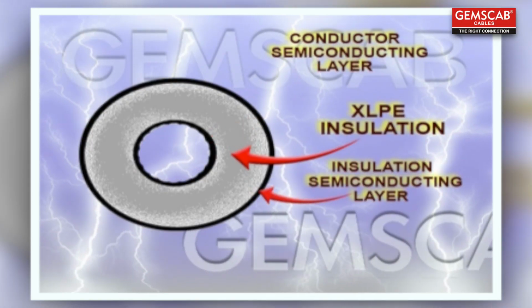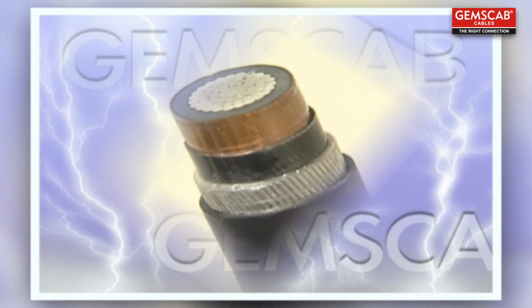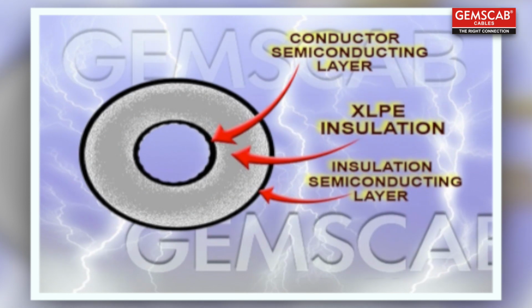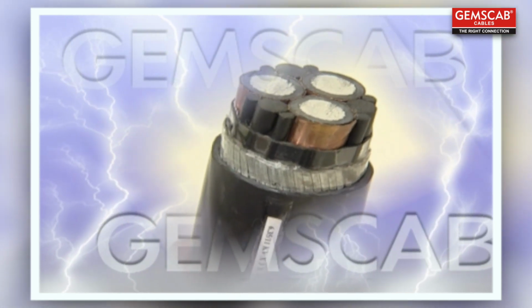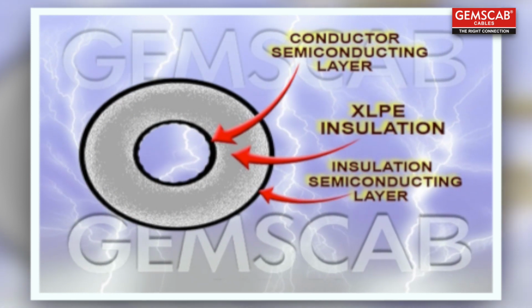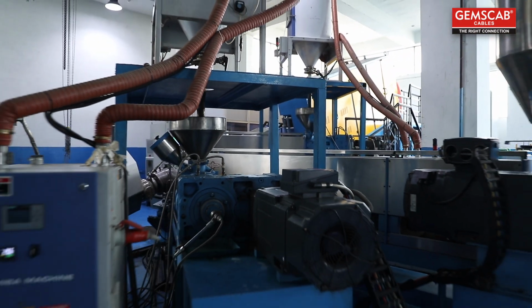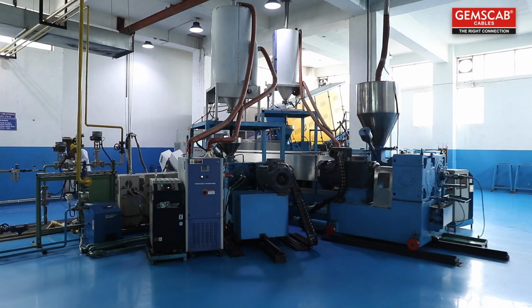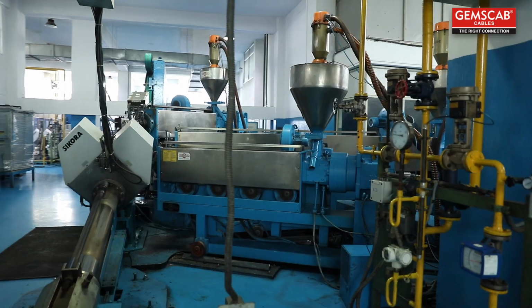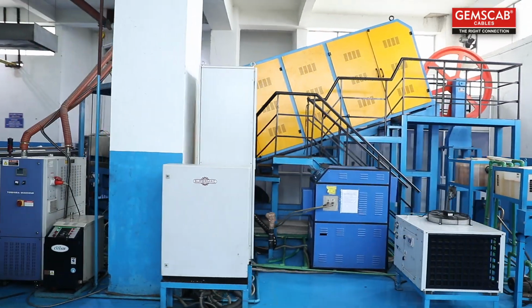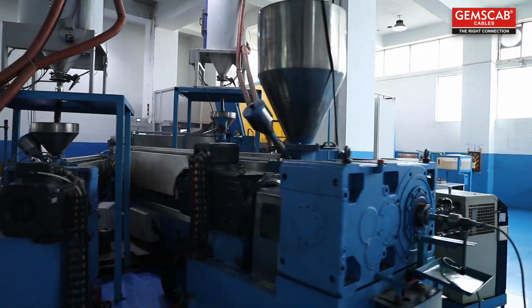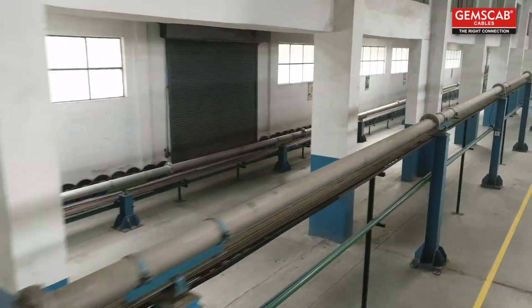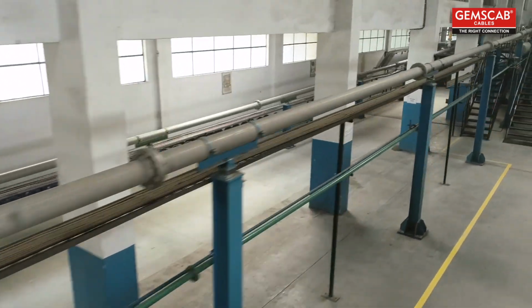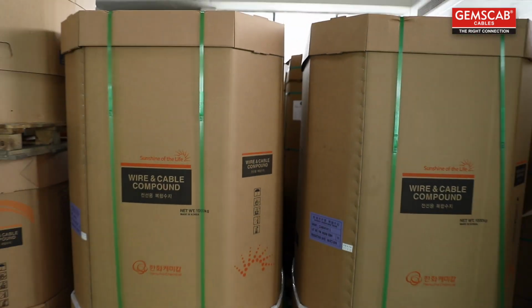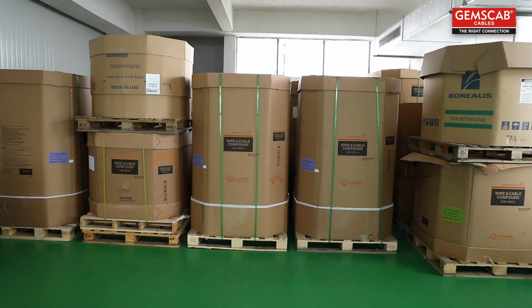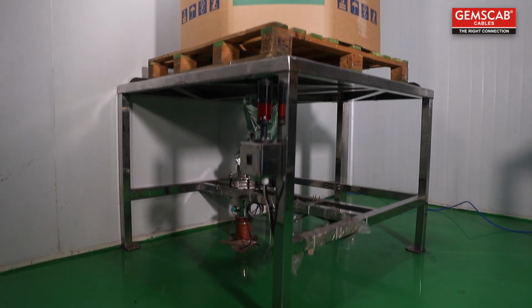The first layer is a semiconducting compound applied over the conductor, followed by the XLPE insulation. A final semiconducting layer is applied over the XLPE insulation for added protection. This crosshead is specially designed to feed 3 compounds from 3 extruders at one point, described as single-point triple extrusion. This extrusion method ensures that the conductor screen and insulation are processed in a single operation to achieve uniform and homogeneous bonding of interfaces. The compound is stored in clean rooms having cleanliness of ISO class 6 and then gravitationally fed directly into extruders for extrusion.